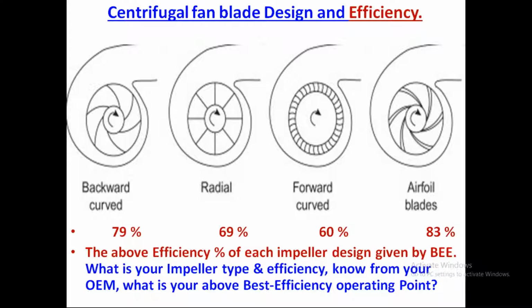Forward curved fans were used in some HVAC installations before, I'm talking about 10 years back, in all the old buildings. In many of the buildings, they are using these forward code fans, which are at 60% efficiency. If they replace them with airfoil blades, especially in the HVAC segment, straight away they can save around 20% just by changing, replacing the impeller.